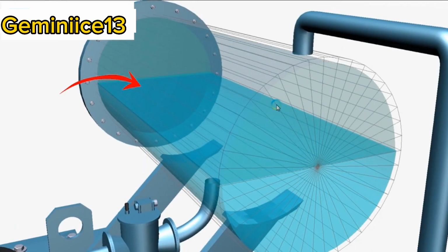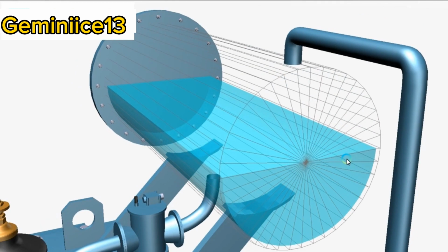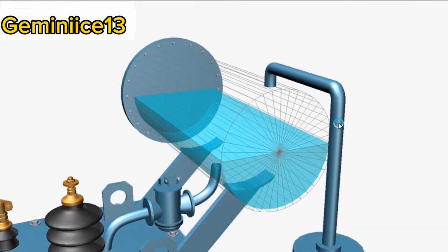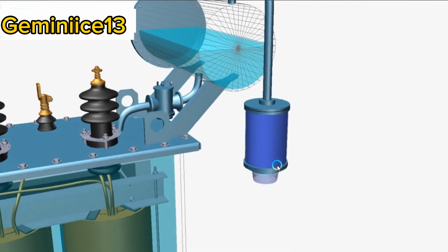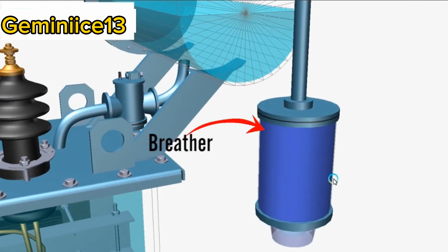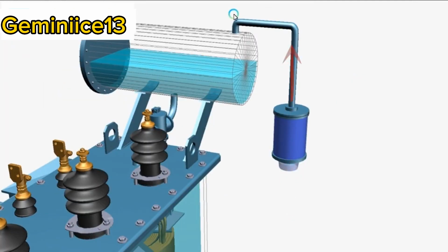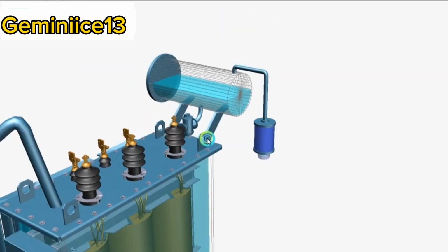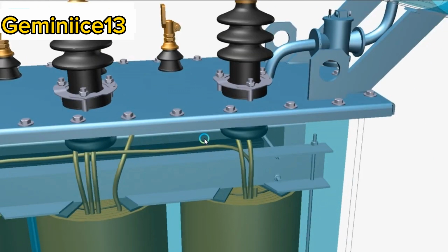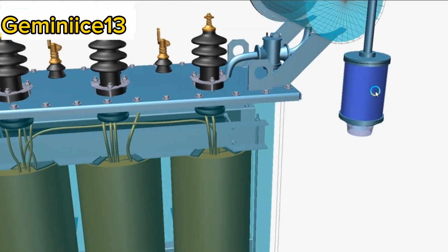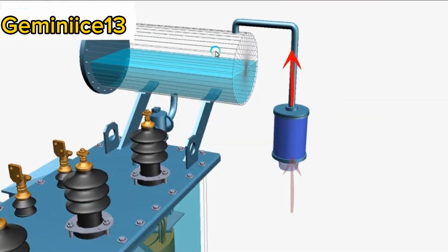That's why in the conservator tank there is extra space, okay? And the space is filled with air. The space is filled with air, obviously there is a gap. The gap cannot be empty. Breather is a device which is used for breathing of the transformer. It means air goes in or out of the transformer. So when the hot oil expands, air goes out from the transformer, and when the oil contracts after cooling, the air enters the transformer.